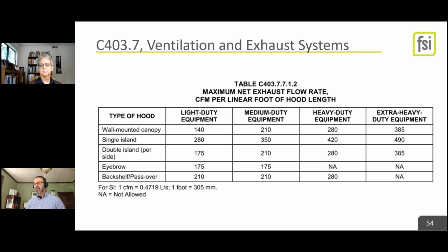Okay, jumping back in. Kitchen hoods have very, very prescriptive CFM per linear foot of hood length that they are expected to meet. If you don't meet that, then you've got to justify why. And there are added hood controls, and heat recovery may be required depending on how you're doing. And heat recovery on kitchen hoods is not always straightforward for grease-laden air exhaust.